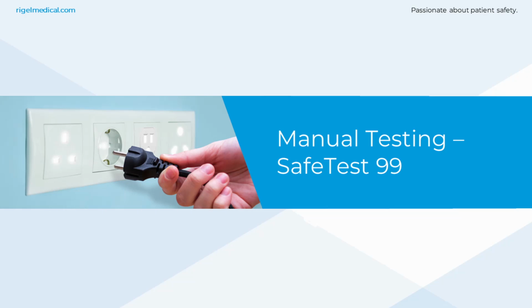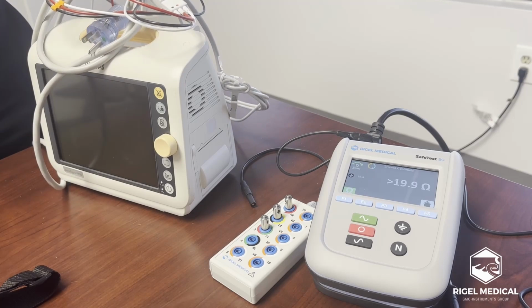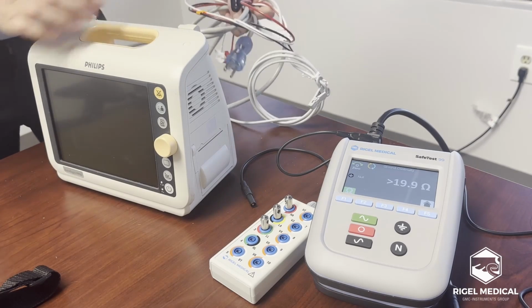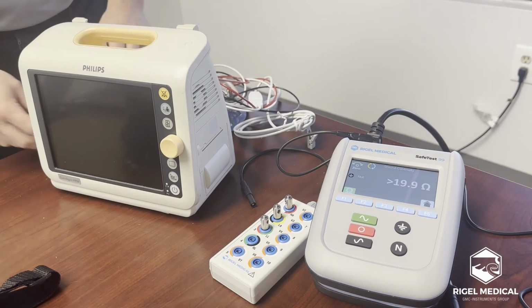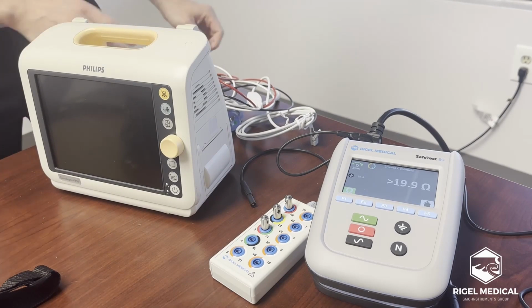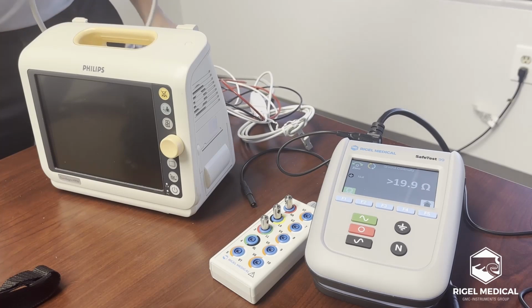So now I'm just going to go into a demo of the SafeTest 99, and this is our manual electrical safety analyzer with applied patient lead connections. So I've just run through that demonstration, and it follows all the NFPA 99 tests we've just gone through in the presentation. Okay, that's good. And one of the most important parts about an electrical safety test is the initial visual inspection.